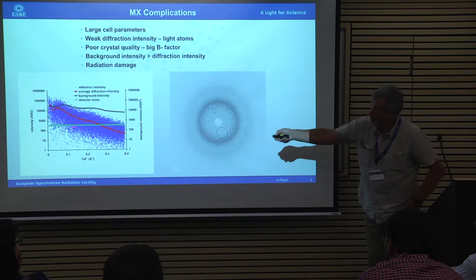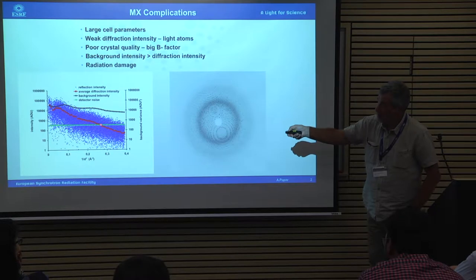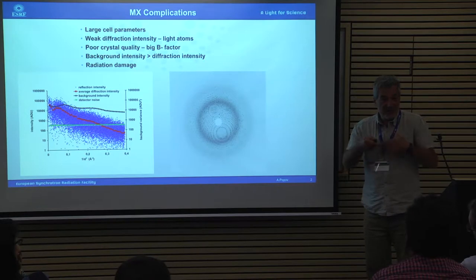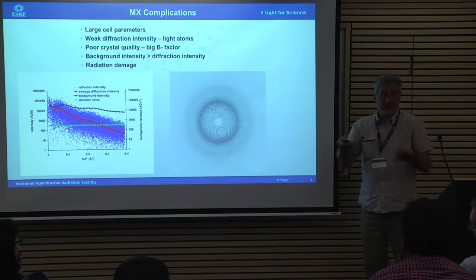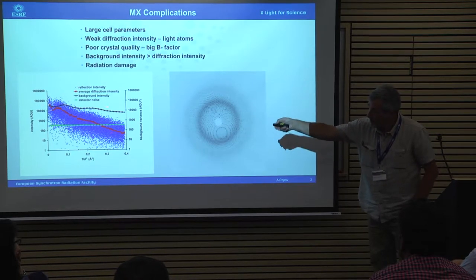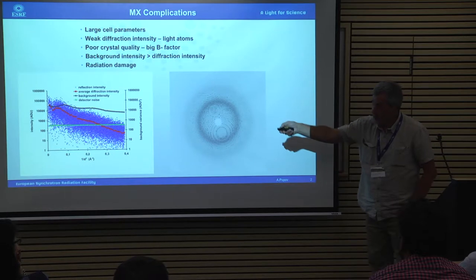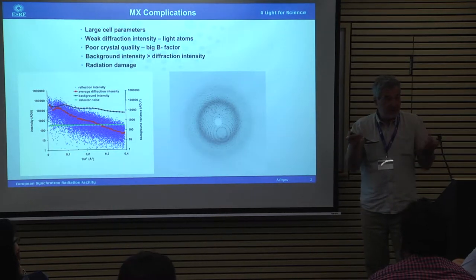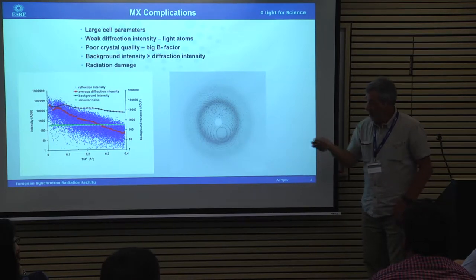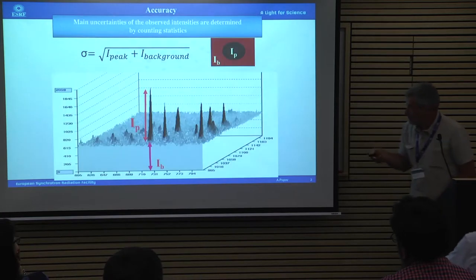The black curve represents the background intensity — as you can see, most diffraction intensities are weaker than the background. This is an old picture because the green line represents a CCD detector, which introduces additional noise from the detector itself. Now we have the Pilatus detector, which has zero readout noise, so the noise floor is lower. This is why the Pilatus is such a good detector — we can significantly increase our ability to measure very weak reflections.